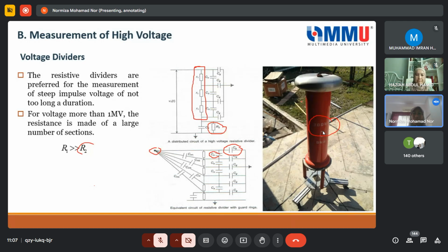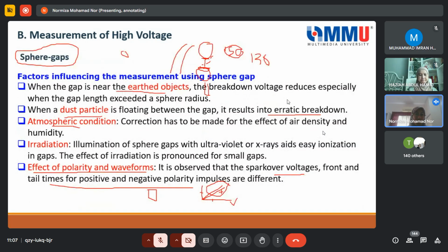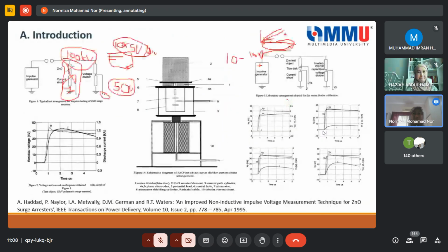But of course, as a user, like in our case, the first thing when this equipment arrives is we do the calibration. Calibration, as I mentioned, is easy. Sorry, I just have to go to the circuit so you understand what the calibration test means. I know that some of you may be familiar already, but calibration is easy. You remove the test object, and then you directly connect one divider here and another divider here. Then you connect the voltage applied from the impulse generator. Then you can plot one from voltage measuring device A, and another from voltage measuring device B. And then we see which one is closer to the input voltage or the charging voltage.